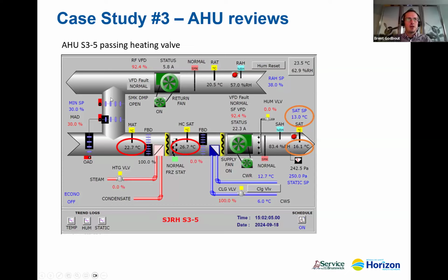Here we have our return air coming in. We're mixing some of that air into our unit. Then we're bringing fresh air in as well. This is the middle of the summer, so it's 23.5 degrees outside. And our temperature indicator before our heating coil is at 22.7. After our heating coil, we're at 26.7. But our heating coil valve is closed. It's summertime, so it should be. We don't want that heat. So we're adding heat to our air handling unit, unwanted heat.